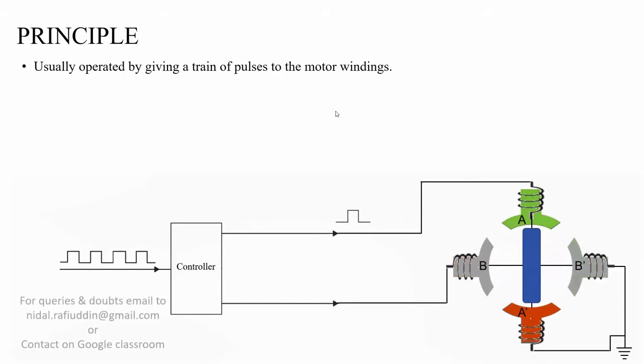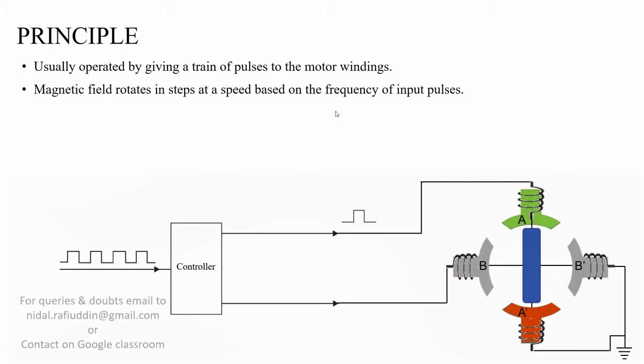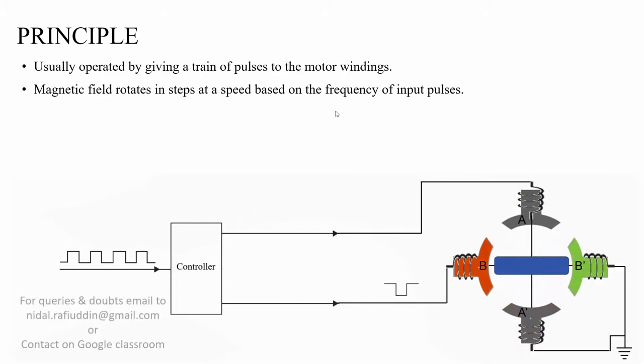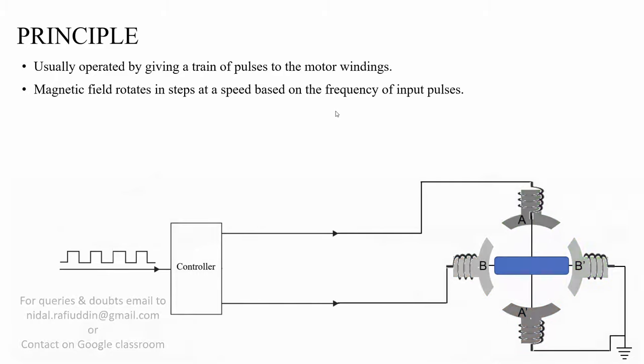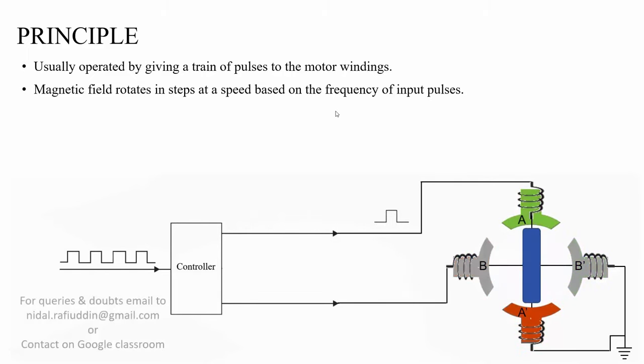Stepper motors are usually operated by giving a train of pulses to the motor windings, which causes the magnetic field to rotate in steps at a speed based on the frequency of input pulses. If the frequency of input pulses is large, the rotating field produced inside will have a large speed. The rotation of the magnetic field inside the stator depends upon the frequency at which the input pulses are given to the stator windings.